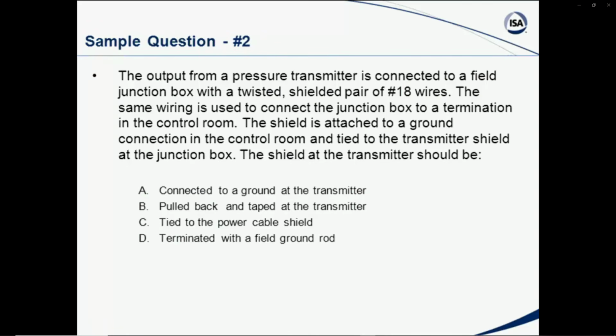Number two, the output from a pressure transmitter is connected to a field junction box with twisted shielded pair of number 18 wires. The same wiring is used to connect the junction box to a termination in the control room. The shield is attached to a ground connection in the control room and tied to the transmitter shield at the junction box. The shield at the transmitter should be connected to a ground at the transmitter, pulled back and taped at the transmitter, tied to the power cable shield, or terminated with a field ground rod.